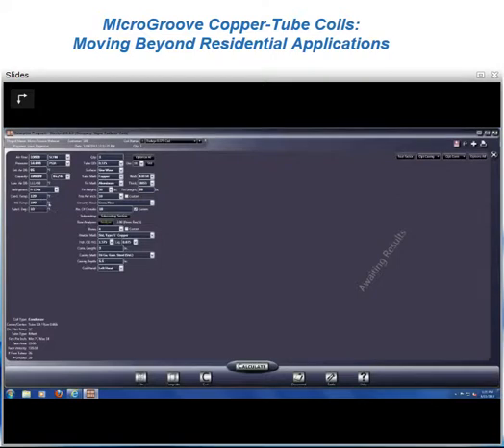And then the condensing hot gas temperatures. These items will remain constant through the balance of the analysis. As we mentioned, we're going to start with our 3/8 tube coil. If you are in an older system, we could model 1/2-inch tube as well, so you see that selection in the drop-down box. But for our initial run, we'll take a look at the 3/8 tube coil.